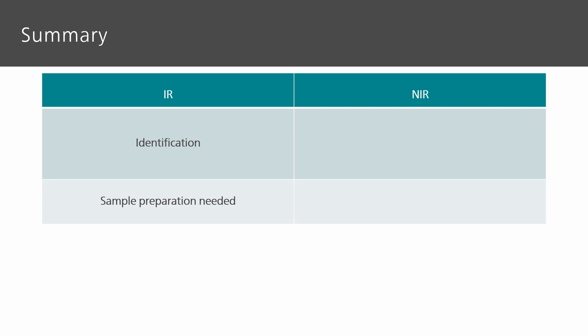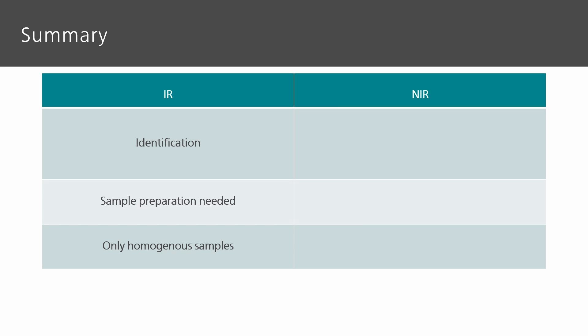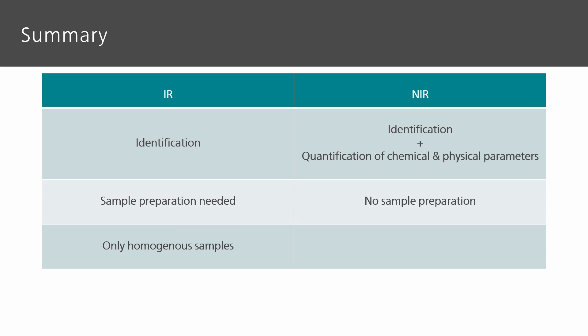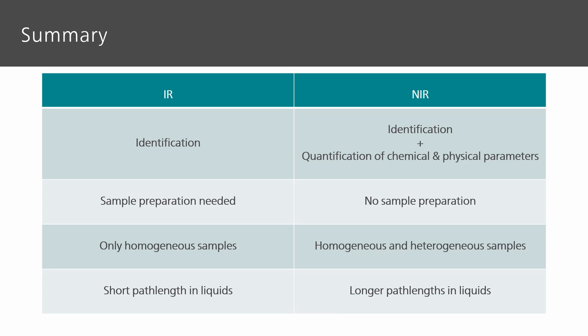To summarize, IR spectroscopy is well suited for the identification of substances. However, sample preparation is usually needed, but can be time consuming. Also, the analysis of heterogeneous solid samples is a challenge for IR spectroscopy. On the contrary, NIR spectroscopy can be used for the identification of molecules and quantification of chemical and physical parameters, without needing any sample preparation. Because of the increased penetration depth of the NIR light, the analysis of heterogeneous solid samples is also possible. When dealing with liquid samples, longer path lengths can be used for NIR spectroscopy compared to IR spectroscopy — a strong argument for using NIR spectroscopy for online measurements in industrial process environments.